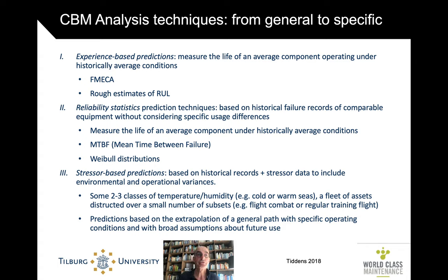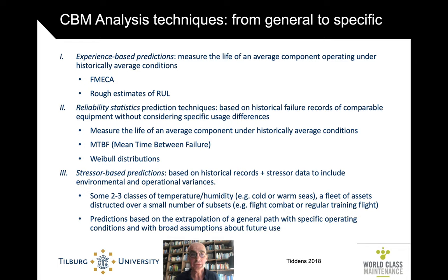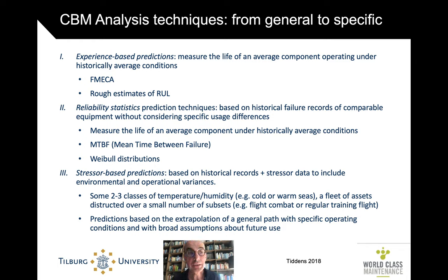You can also do statistical analysis of data that you have. Using historical failure data — how often did this equipment fail over a certain time interval — gives you the mean time between failure. That's over a population of components under historically average conditions. You can try to fit that to a Weibull or other statistical distribution to also make predictions about non-observed values.